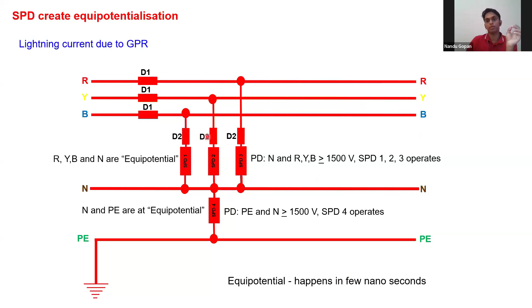You'll actually be confused on how to select the current I nominal or I imp of the surge arresters. How do I check it? How do I select it? Should I have 200 kiloamps, 100 kiloamps, or 50 kiloamps? What should I do? That actually depends on how the risk assessment is done.